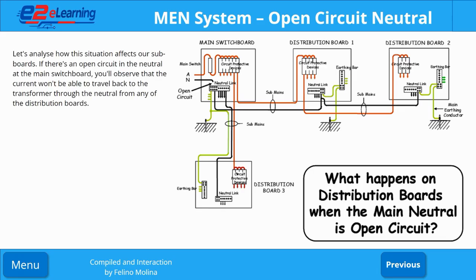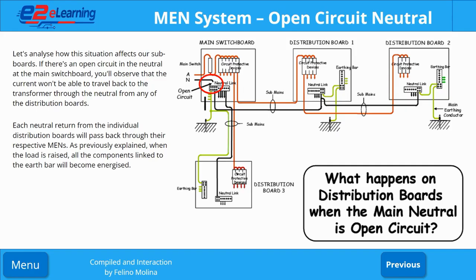Let's analyze how this situation affects our subboards. If there's an open circuit in the neutral at the main switchboard, you'll observe that the current won't be able to travel back to the transformer through the neutral from any of the distribution boards. Each neutral return from the individual distribution boards will pass back through their respective MENs. As previously explained, when the load is raised, all the components linked to the earth bar will become energized.